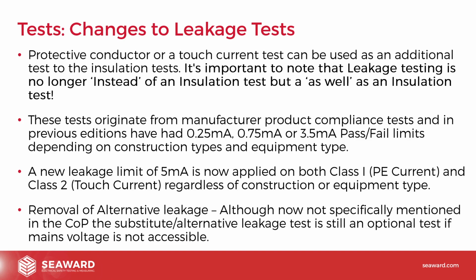The leakage tests originate from manufacturer production compliance tests. Generally the origins of the tests, certainly the ones applied under the 4th edition, were done by manufacturers in laboratory or production environments using quite complex test equipment, often wrapping things in tin foil and all sorts of methods needed to achieve these values. These values were then taken and put into the code of practice. In the previous editions, we had pass-fail limits of 0.25 milliamps for Class 2, 0.75 for Class 1 portable or movable equipment, and for stationary equipment, portable handheld was 0.75, movable stationary was 3.5.